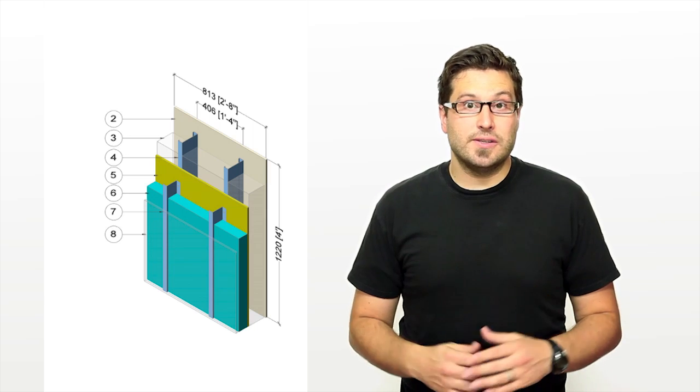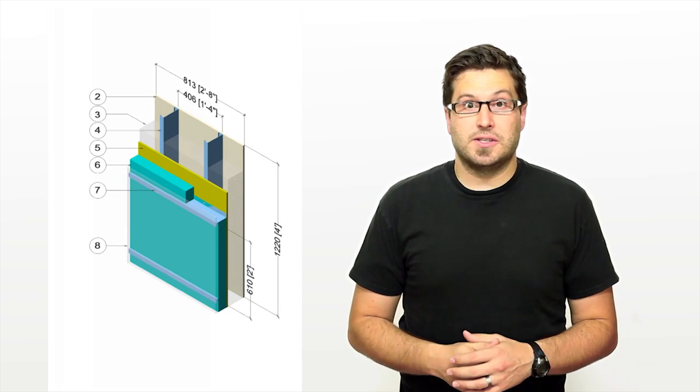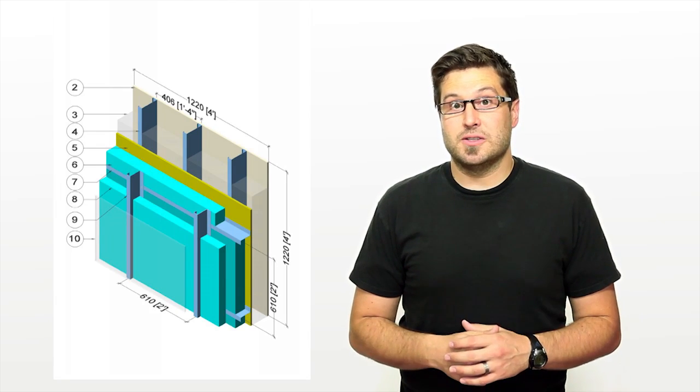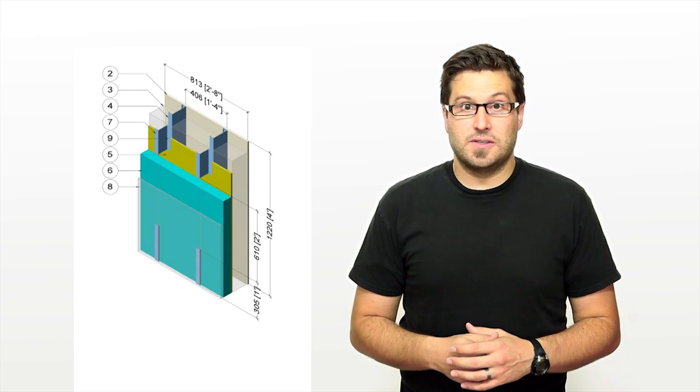In addition to vertical Z-girts, they modeled horizontal Z-girts, vertical and horizontal Z-girts, and intermittent Z-girts. When we were doing this modeling, we found that with one of the common systems, the vertical Z-girts, heat transfer was about twice as much as some of the better systems we tested.